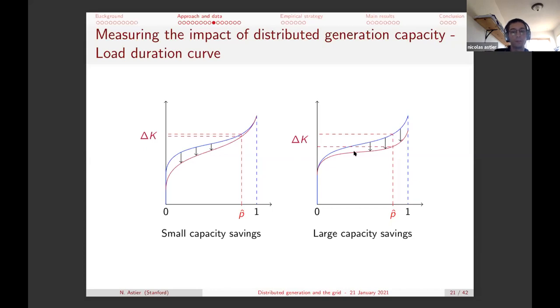As a grid planner, the impact of this unit is very different depending on when it produces. If it produces predominantly in hours during which load was already low, so it shifts the lowest quantiles more, you will indeed have a shift downward of the load duration curve, but the capacity savings you get are pretty low. If by contrast, for the same amount of energy produced, you shift the peak hours more, then you get much, much larger capacity savings. So you really care about when distributed generation produces relative to how high electricity consumption was in different hours for the substation.